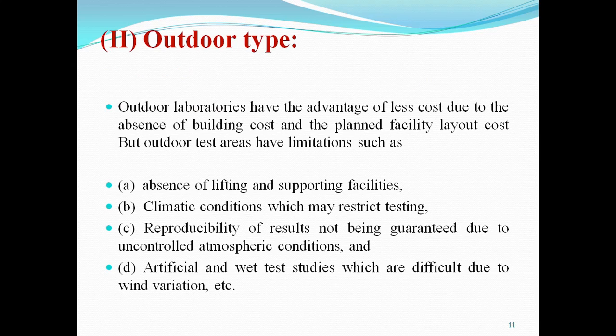Outdoor laboratory. If the equipment is small, we can install it in an indoor laboratory, but for a very big, large-size laboratory, we have to go for the outdoor type. Outdoor laboratories have the advantage of less cost, due to the absence of building cost and plant facility layout cost.